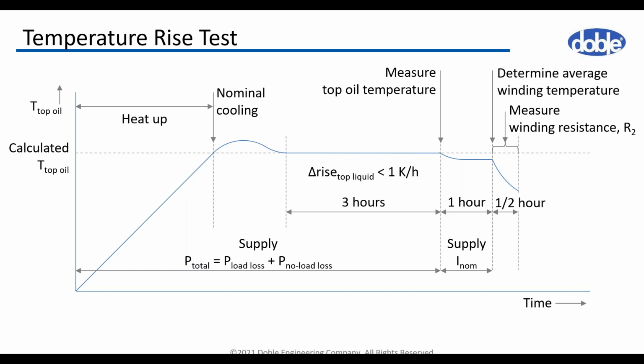After that, we can reduce to rated current for 1 hour in order to determine the average winding temperature by measuring the winding resistance for a period of, let's say, half an hour. And based on this resistance, we extrapolate to the moment of shutdown, and based on the resistance at the moment of shutdown we obtain the average winding temperature.